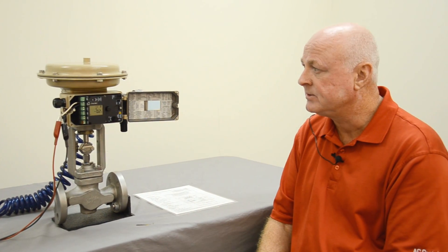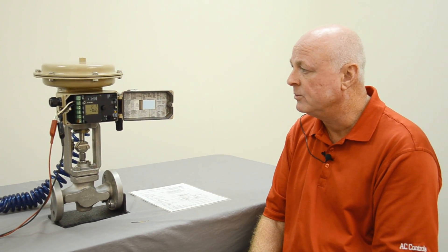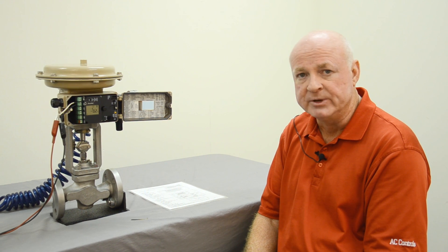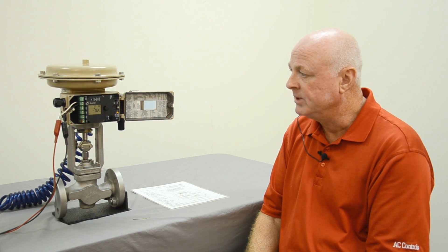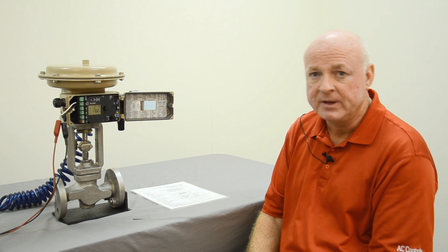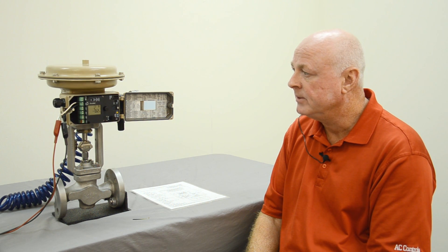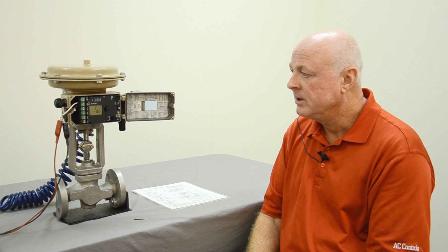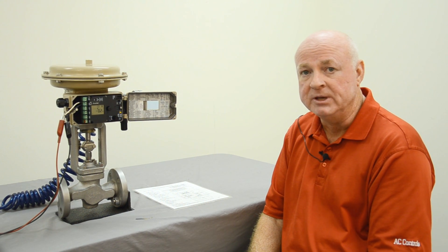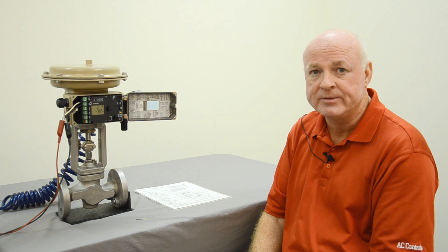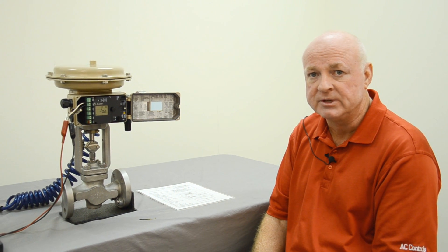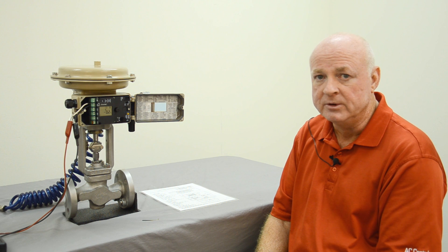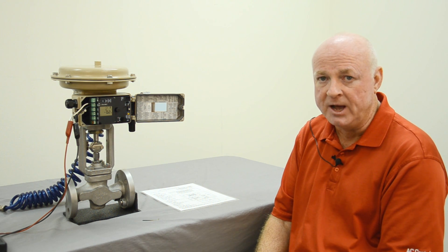In this case, the spring range we're working within is three to fifteen pounds. So our air supply would need to be greater than that. However, in most cases, you don't need to be concerned with the air supply other than the fact that the actuators and positioners cannot handle over a ninety PSI supply.